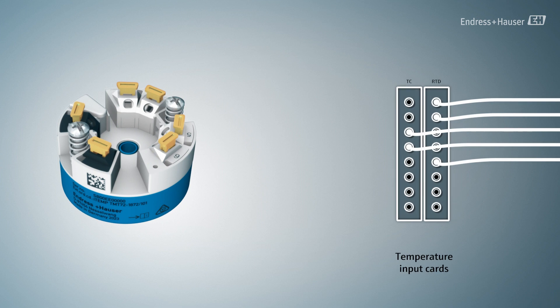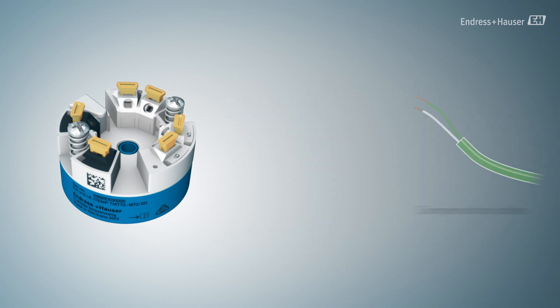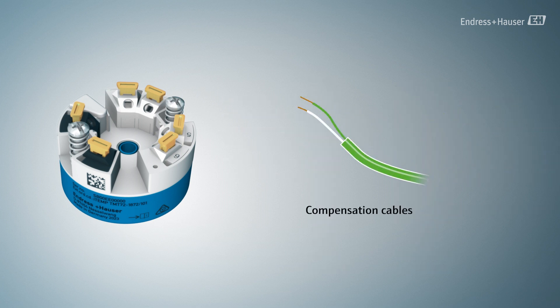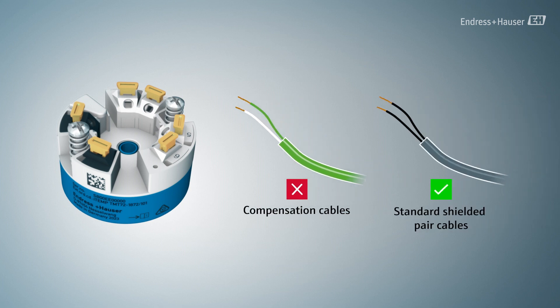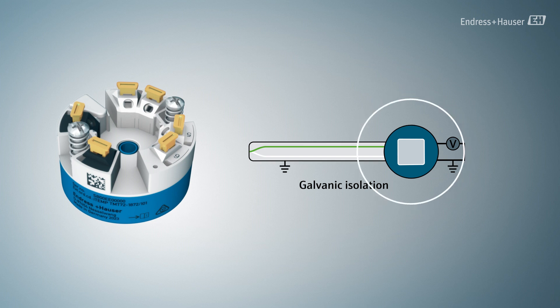The use of temperature transmitters has several advantages over direct wiring. Instead of temperature input cards, a cost-efficient analog input card can be used. Expensive extension or compensating cables for thermocouple measurements can be replaced by standard shielded pair cables. In addition, transmitter features like galvanic isolation help to lower measuring errors by avoiding ground loops, specifically for thermocouples.